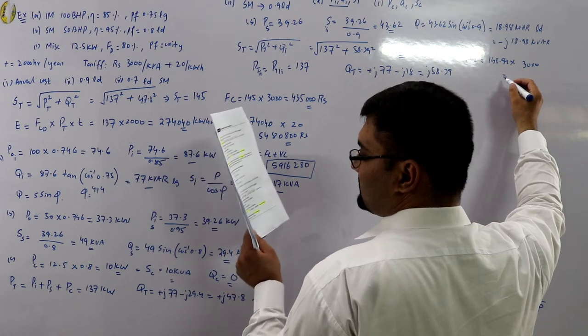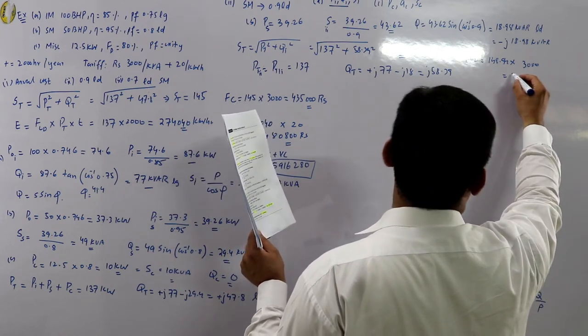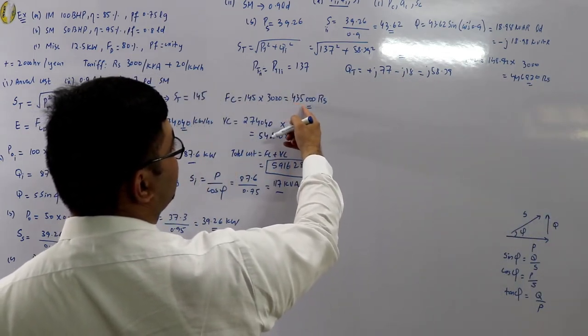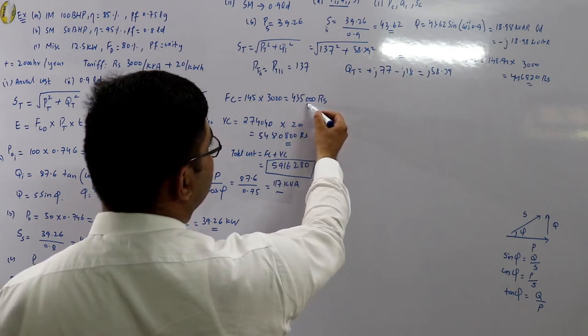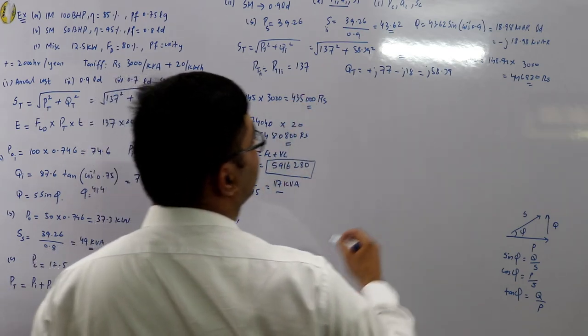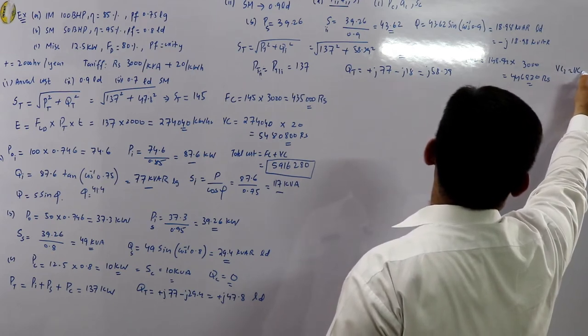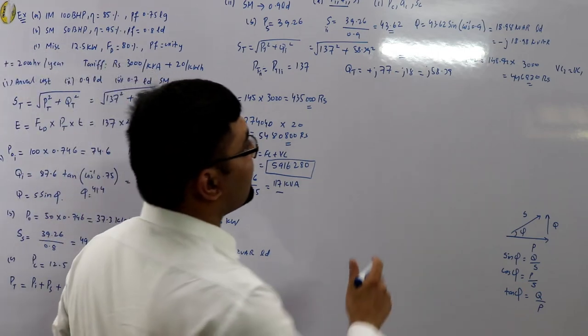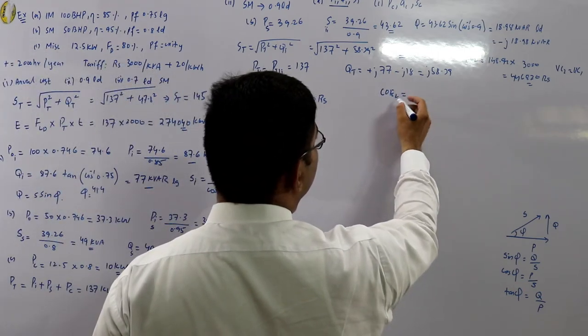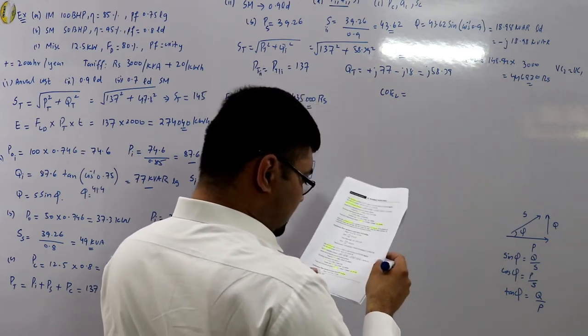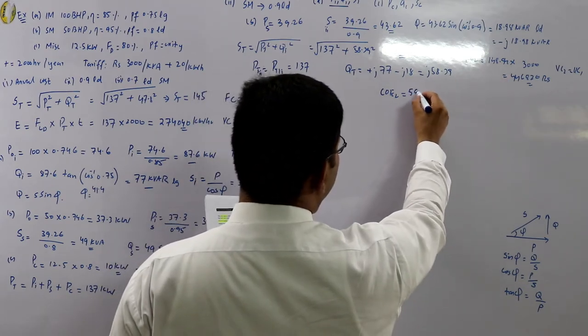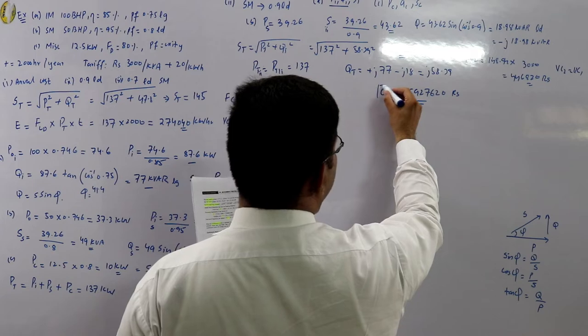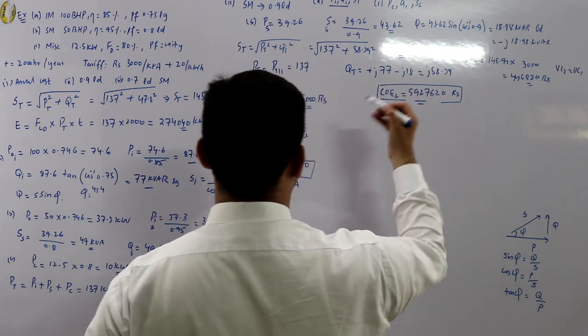The variable cost for Case 2 is the same as Case 1, since energy content hasn't changed. Total cost₂ = 446,820 + 5,480,800 ≈ 5,927,620 rupees. So when the synchronous motor is over-excited to 0.9 leading, the annual cost increases.